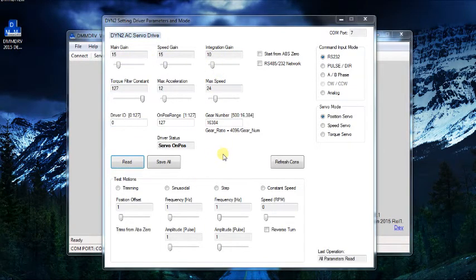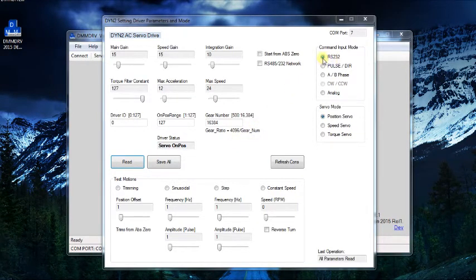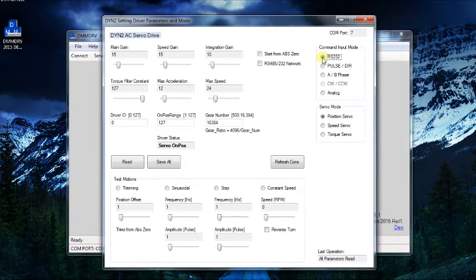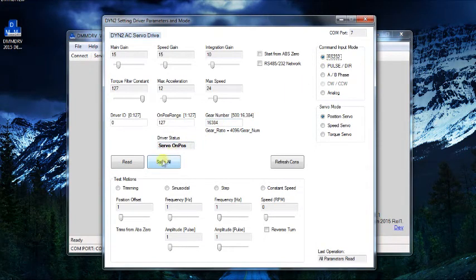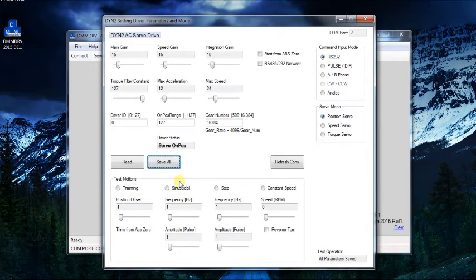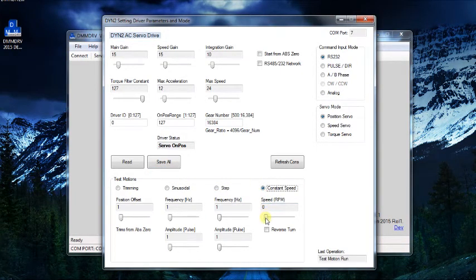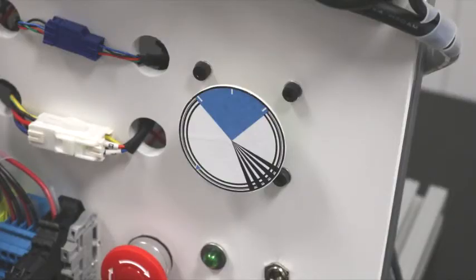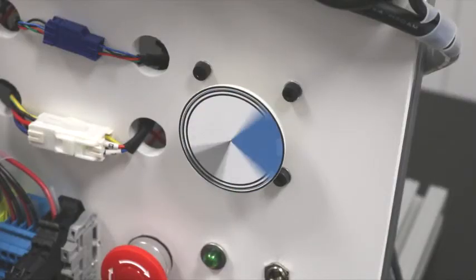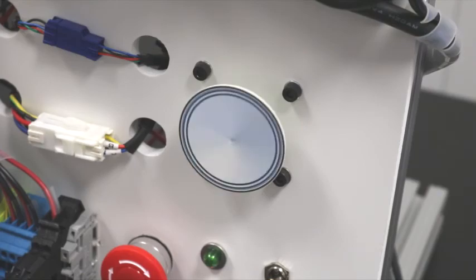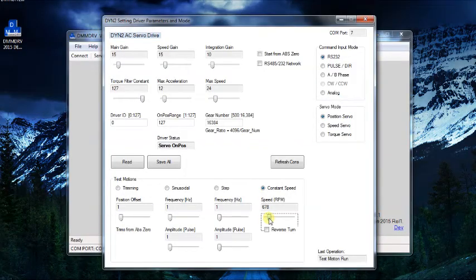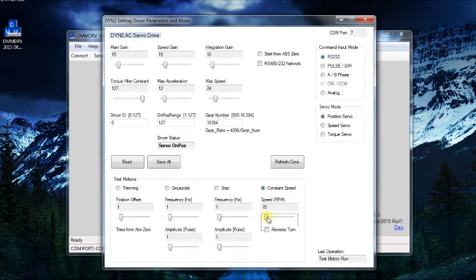To test the motor movement, select RS-232 under command input mode, then select save all under test movements. Select constant speed, then drag slowly the slider up to increase the speed. Use the various test movements to test and verify motor performance.